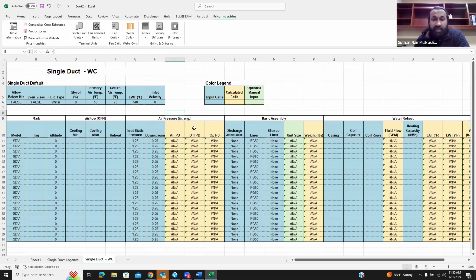So right here, we have a few different cells with three different colors. The blue cells are the ones where we input our parameters. The orange cells are the calculated cells. And the green one, I would call an optional manual input or override cell, which is only on the unit size, because I've seen a lot of engineers who want to have their own size. Say I get a performance from a size 4 VAV box, they would still put in a size 6 there. So that's why we have it as an optional manual input or override cell. So let's run with an example.